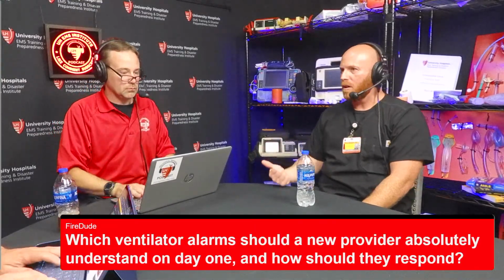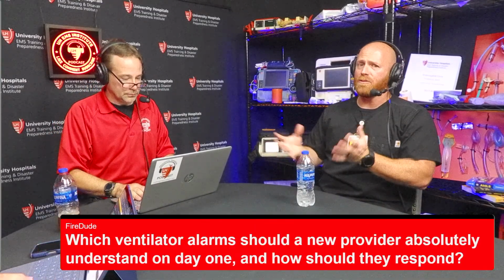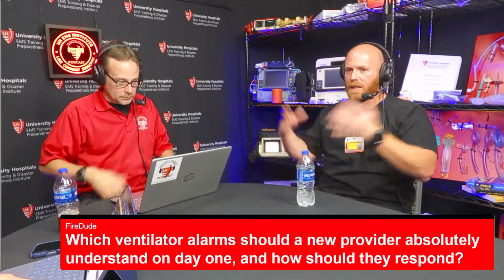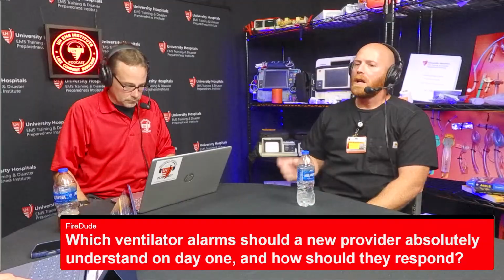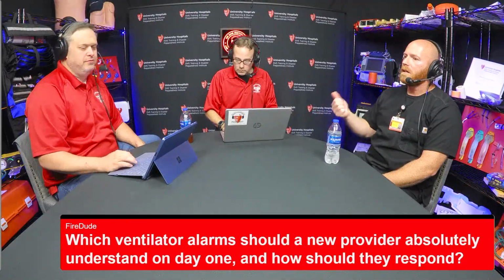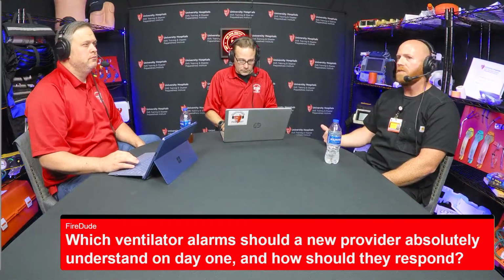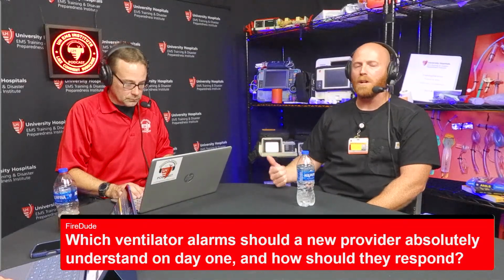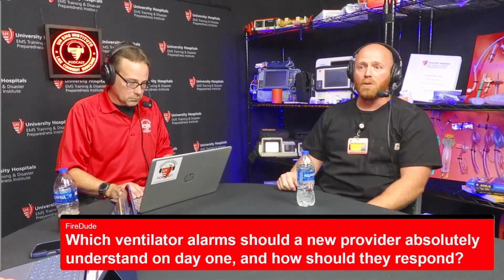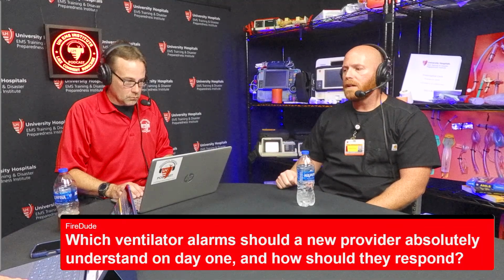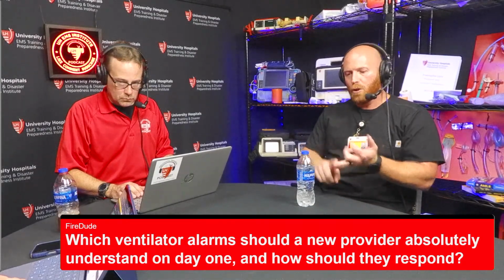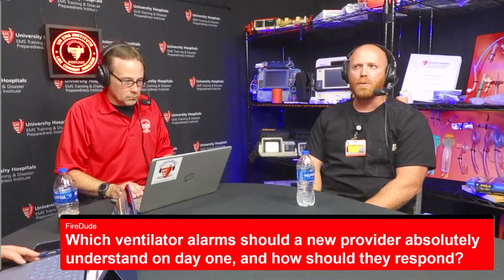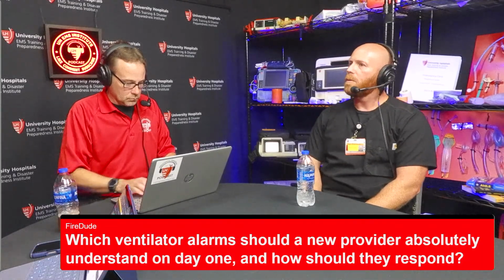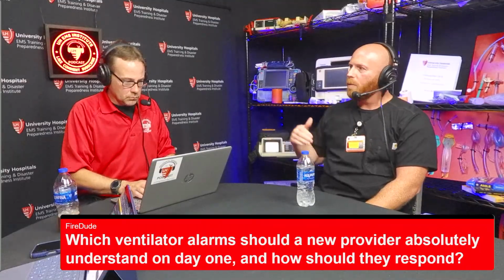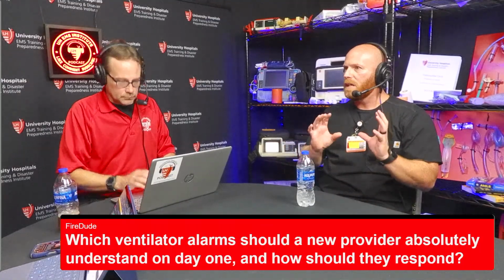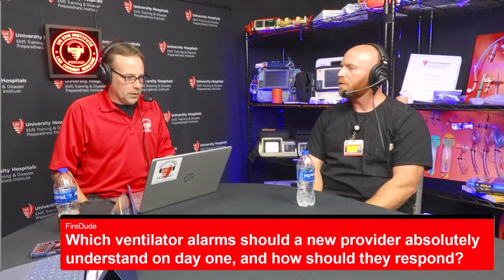Number one is your pressure alarms. And the caveat to this is that those alarms have to be set appropriately, because if they're not set appropriately, it doesn't do you much good, right? So same thing as a monitor, right? Yeah, right. So high pressure alarm is important to pay attention to, because if we overpressurize somebody's lungs, we're going to potentially blow a pneumo and cause more problems for ourselves. And then also low tidal volume, low minute volume. Those are probably the three top most important ones. So we need to make sure that we're not over pressurizing somebody, and we also need to make sure that we're giving the breaths that we are programming the ventilator to do.